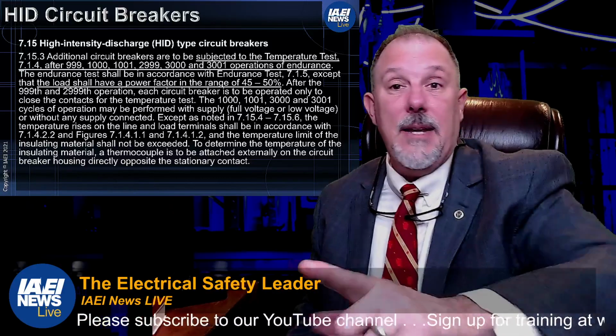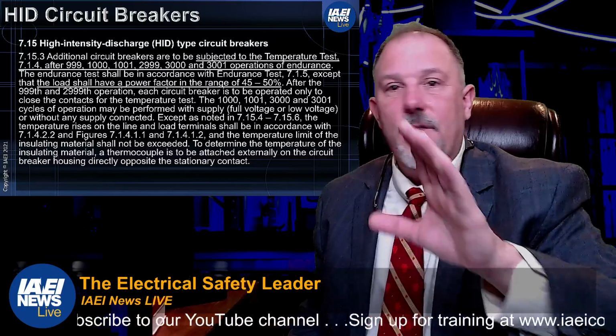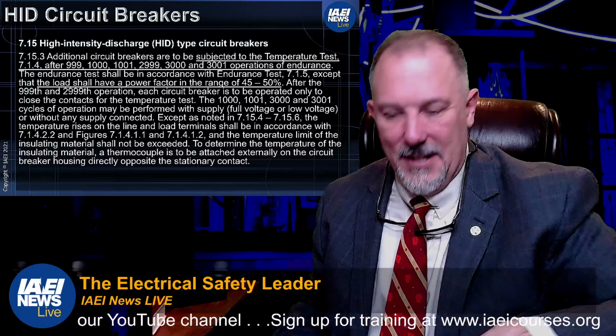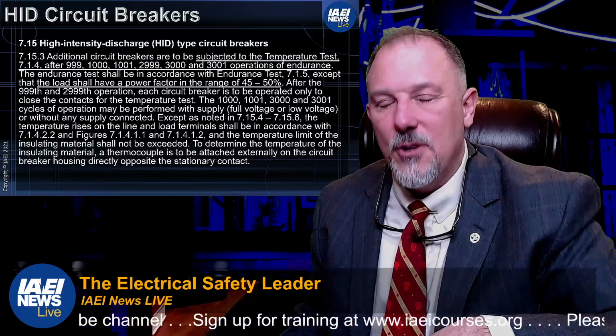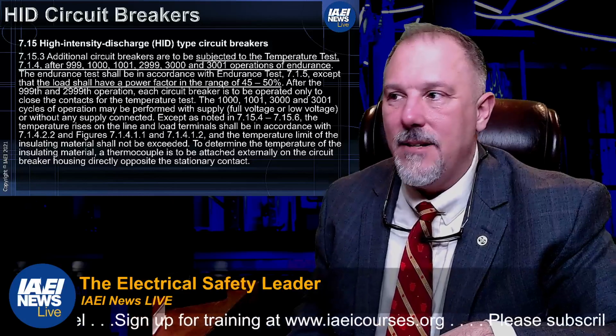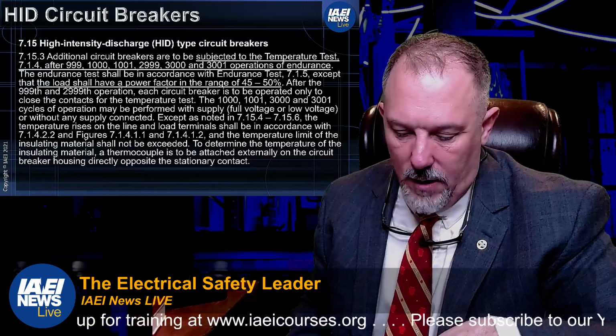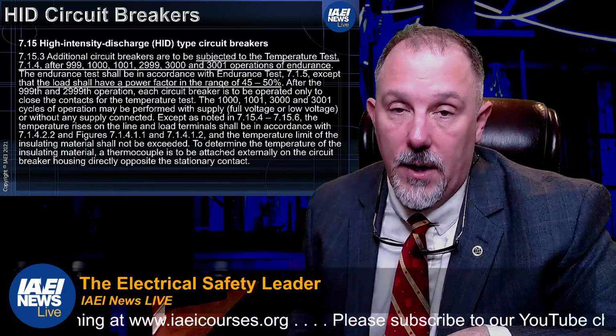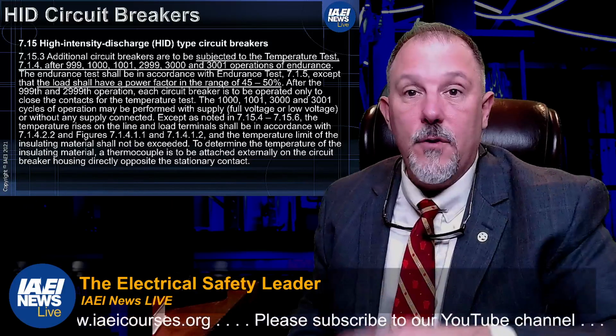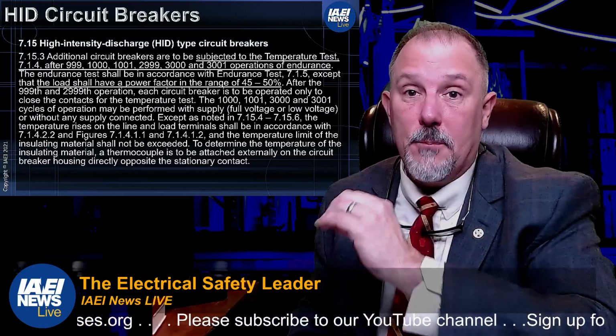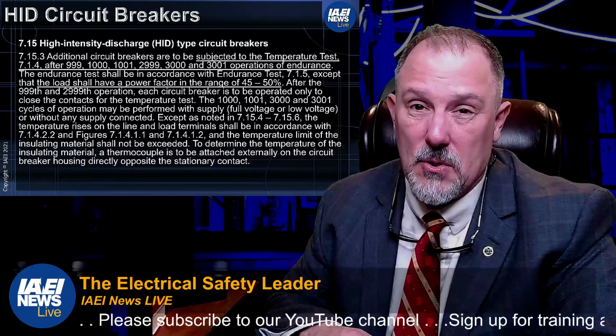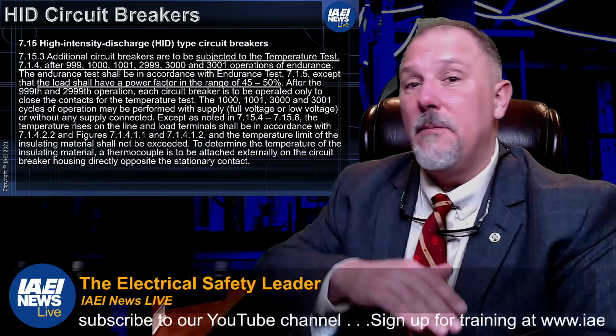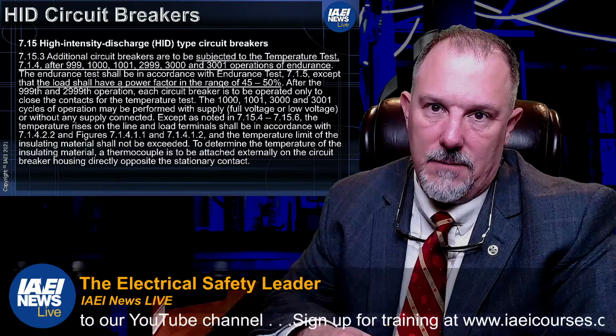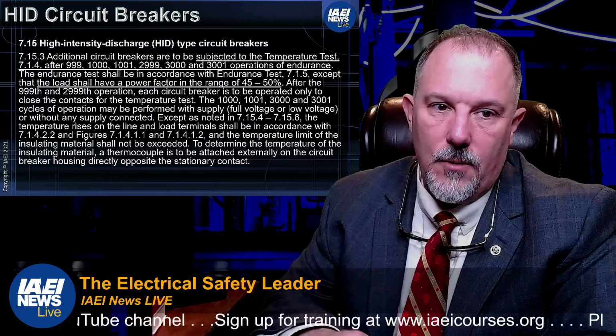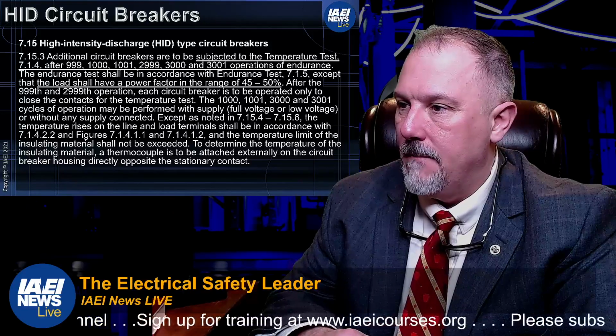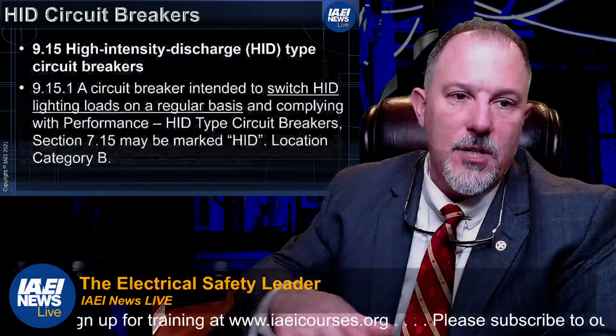So what does that mean? When we were working on our task group for 220, the lighting guys were talking about 1.5 watts per square foot. The actual VA per square foot is twice that. It's 3 VA per square foot because the power factor is 50%. If it was 45%, it'd be a little bit more than 2 times. That's how you can determine that. So that's a key piece of that language in UL 489.